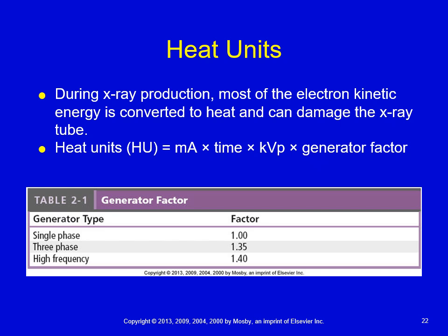Now, not to say that we go into work every day and do calculations on heat units. In fact, some of the equipment available these days actually has a ticker that shows you the heat units generated per exam. You'll notice that with each exam, especially if you're doing back-to-back X-rays, those heat units will tick up, and over time, as the machine sits idle, those heat units will gradually come back down, or bottom out at 0. So you have to learn how to calculate heat units.